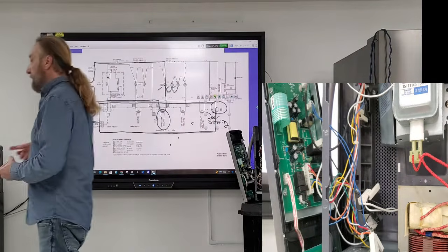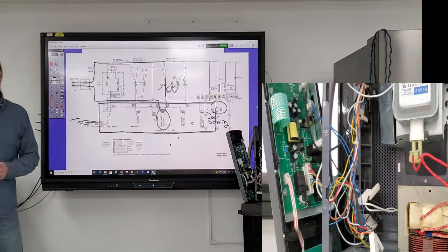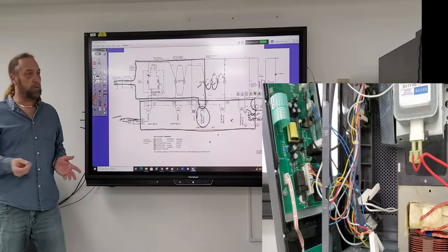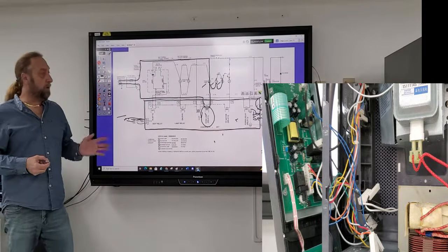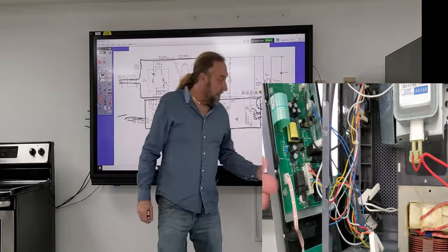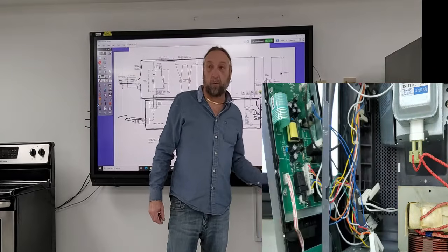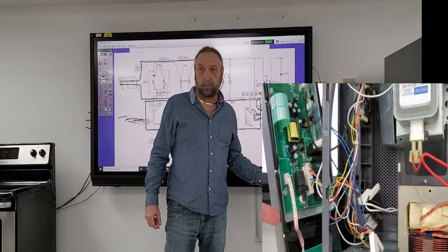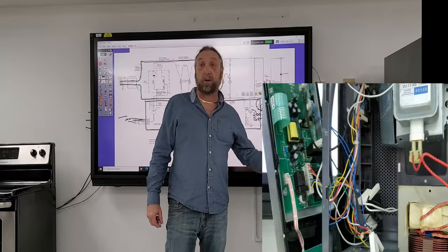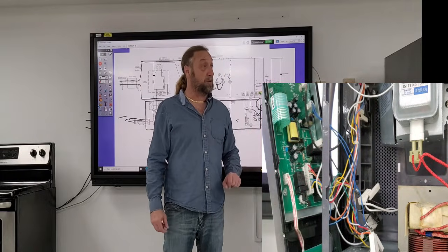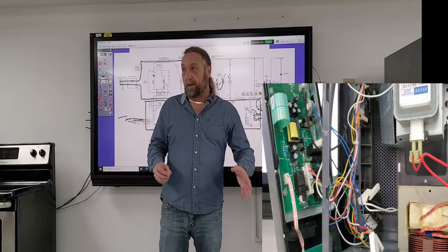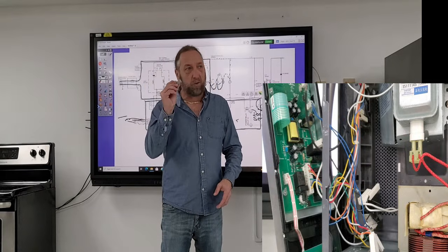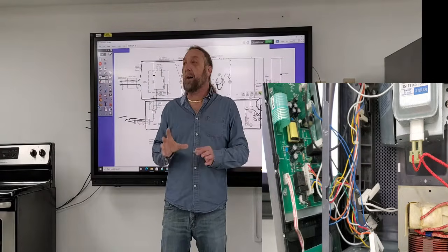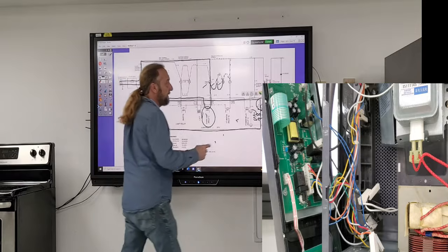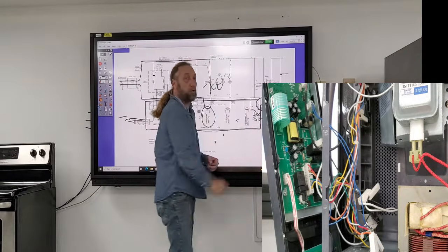Okay, so if all of them are working, it's not a door switch problem. So it might be a magnet — I'm not getting 120 volts to my transformer because the relay's bad, or I'm getting 120 to the transformer but the problem is in one of my high voltage sections. We're not going to talk about that today. But the monitor switch gives you an opportunity to check to see if I'm getting power to my transformer.